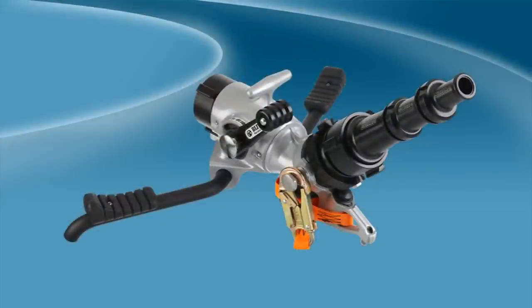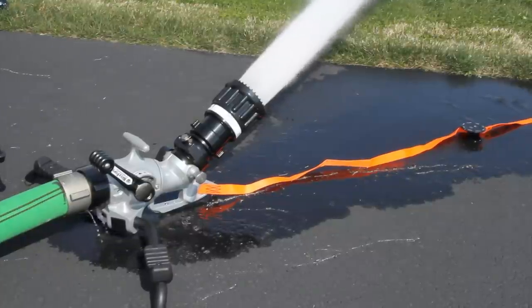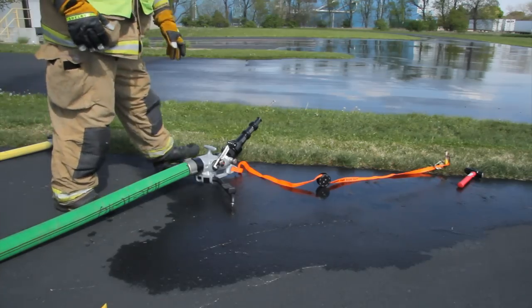The Blitzfire is Task Force Tips' innovative, lightweight, and highly versatile portable attack monitor. Rated up to 500 GPM, the Blitzfire integrates a 2-inch unobstructed low-loss waterway with a ball-style shutoff valve that includes a positive locking detent valve control.